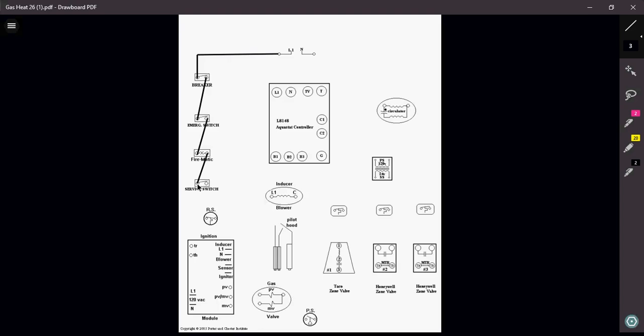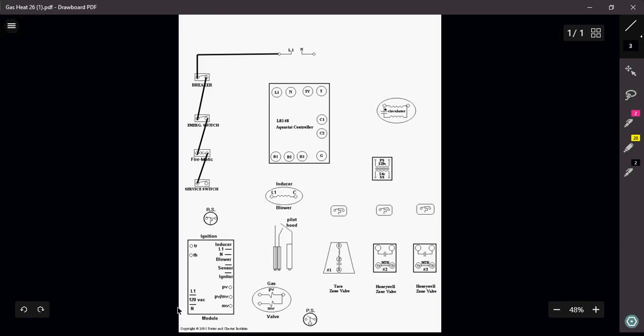Out of that service switch, I have to go in a couple of different directions. In fact, there's actually three different areas that I need to bring 120 volts to. I need to bring 120 volts up to my Aquastat itself, my L1. I also need to power up my transformer over here, and I also need to send 120 volts down to my ignition module.